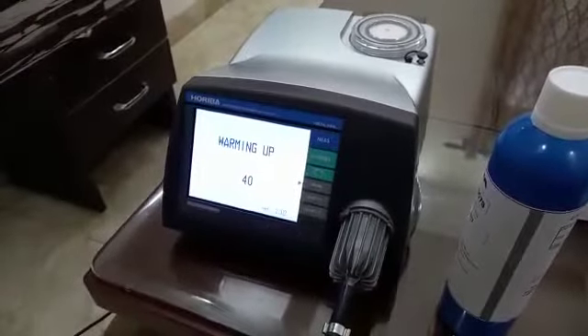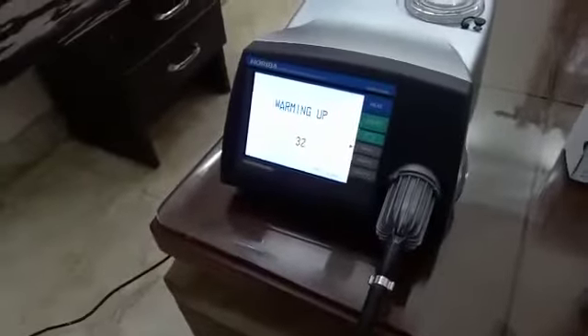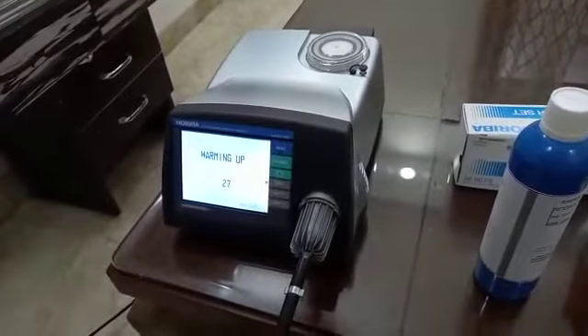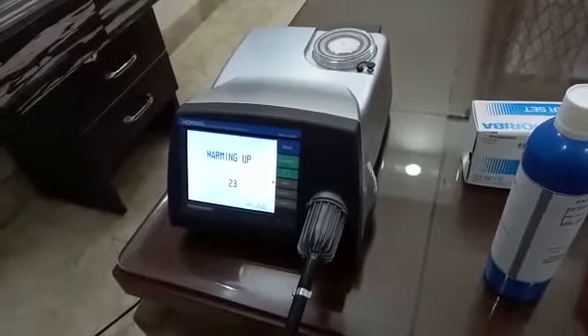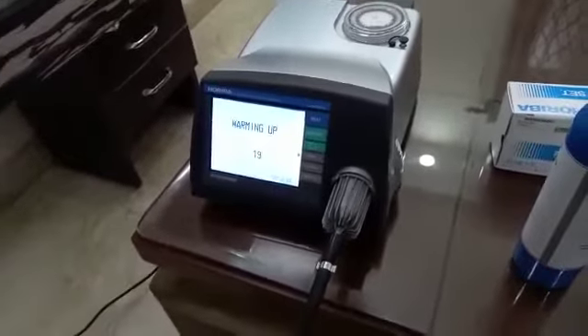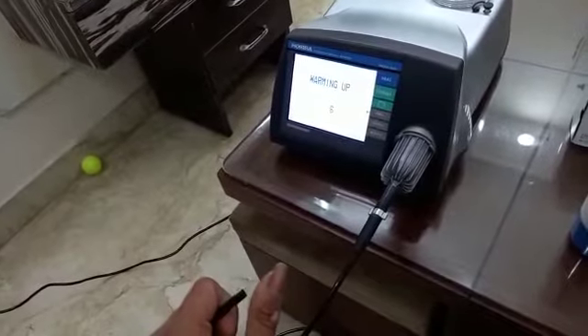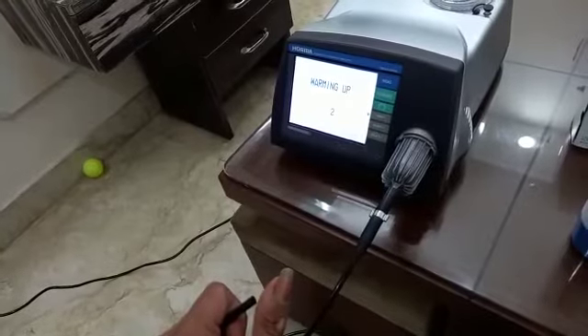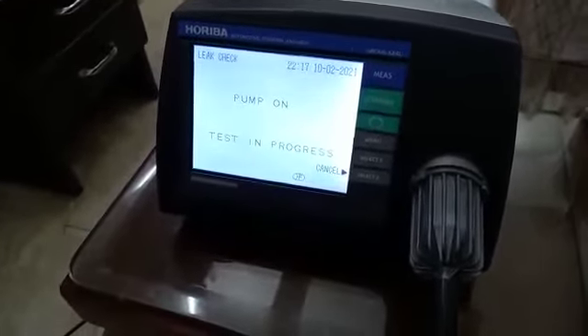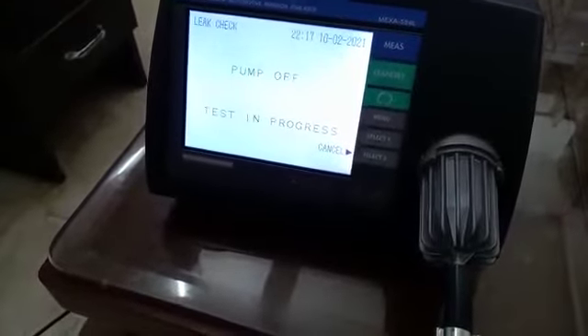Now it's 42 seconds, and the machine is on the verge of getting started. As the time passes, the machine will go to a leak check, for which I will block the sampling probe. Look. As the sampling symbol is coming at the bottom, it shows the line is getting choked. Okay, so now it's showing pass because we have choked the line, and it ensures that there is no leakage.